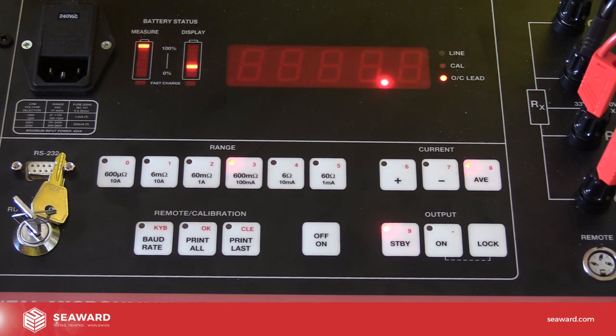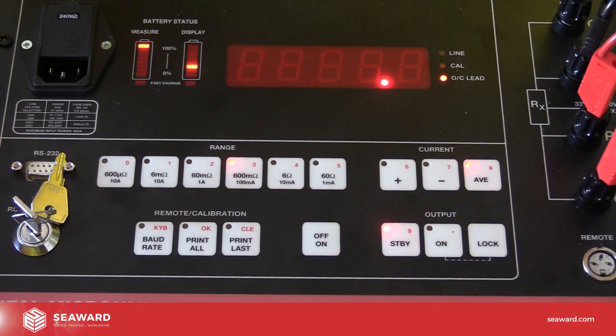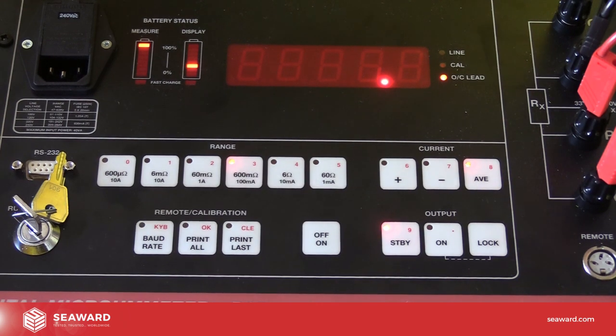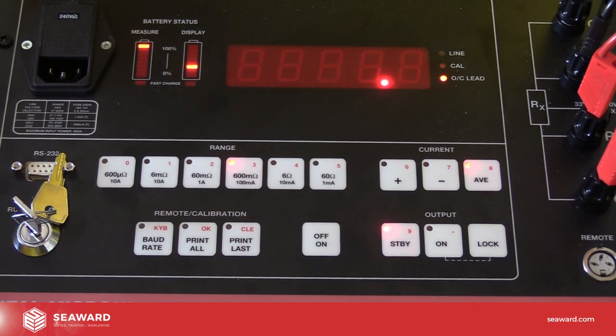So firstly, we're going to discuss the range. Well, as I said before, we're going to be measuring a 10 milliohm resistor. So I'm going to start the range off at 600 milliohms and take a measurement at that range. Next thing to decide is the level of current, whether we want it to be single directional or bi-directional current. I've set mine to average, so we're going to set this to a bi-directional current. It will send the test current from C1 to C2 and take a measurement in that polarity, but then reverse that from C2 to C1 and take a measurement in that polarity and then display back the average.